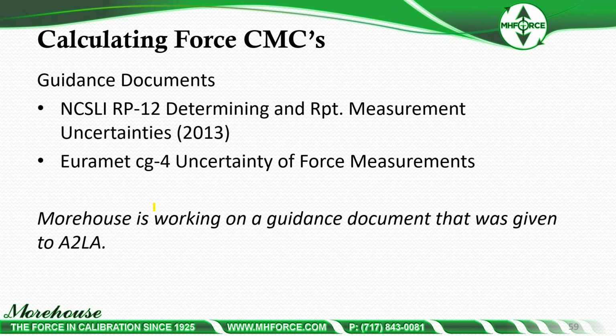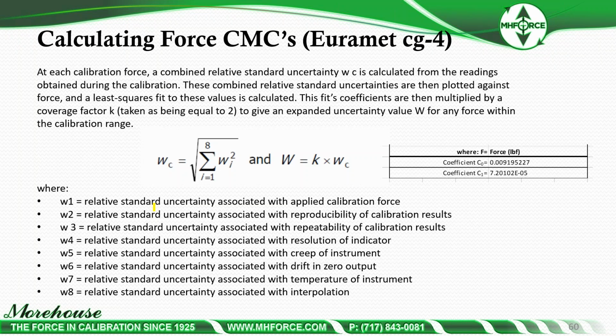And then for ISO 376, I was a bit snarky when I wrote it, and I just said, hey, see Euramet cg-4, uncertainty of force measurements, because that's really anybody doing calibration in accordance with ISO 376 should be using that Euramet guide. But anyway, so you want to calculate force CMCs, Euramet cg-4. We went over these before.